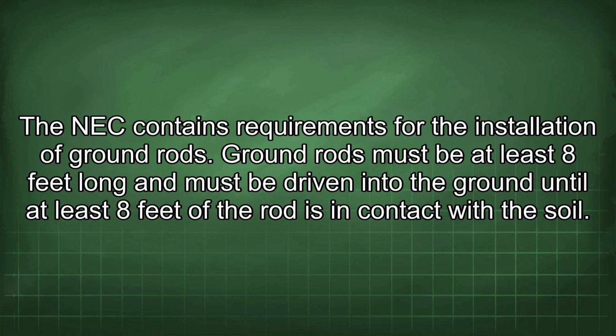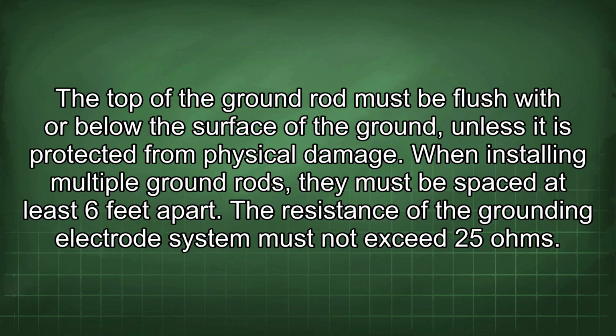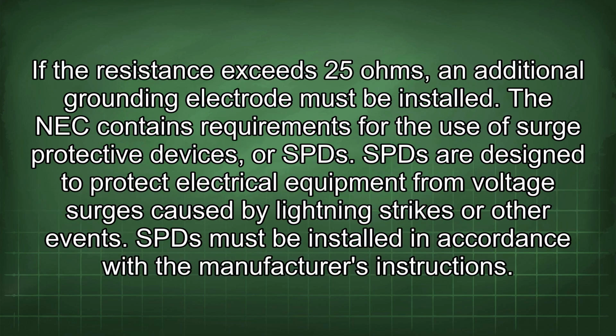The NEC contains requirements for the installation of ground rods. Ground rods must be at least 8 feet long and must be driven into the ground until at least 8 feet of the rod is in contact with the soil. The top of the ground rod must be flush with or below the surface of the ground, unless it is protected from physical damage. When installing multiple ground rods, they must be spaced at least 6 feet apart. The resistance of the grounding electrode system must not exceed 25 ohms. If the resistance exceeds 25 ohms, an additional grounding electrode must be installed.